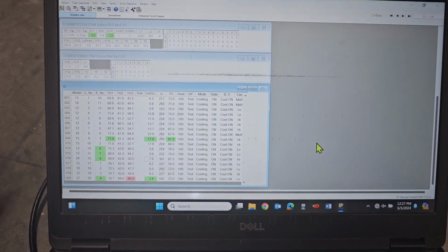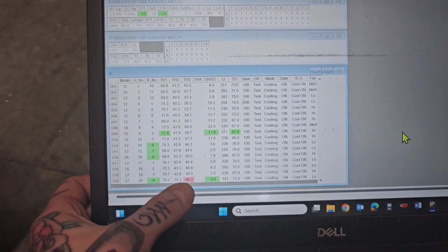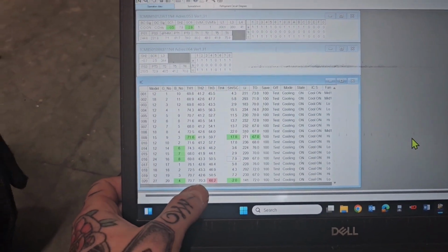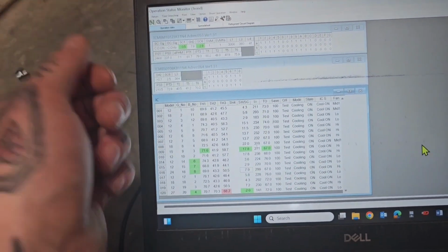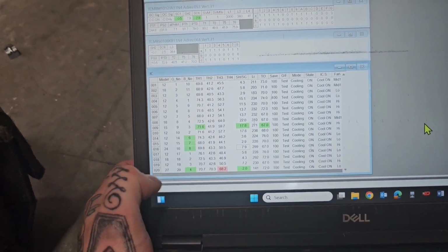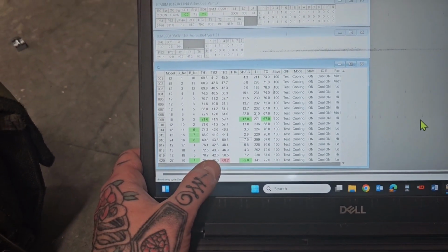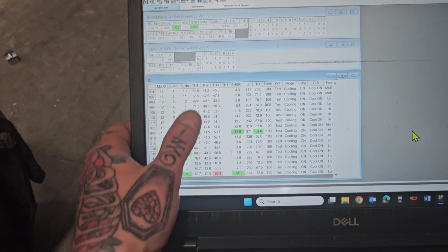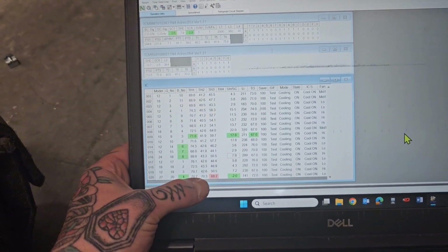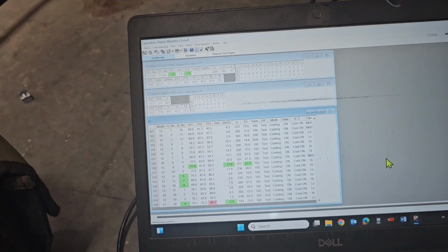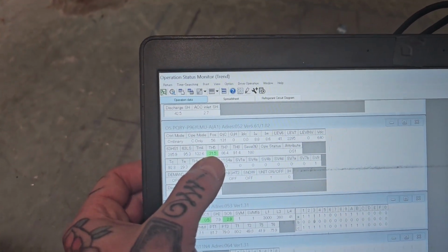If we go forward 10-15 minutes, you can still see, so we've got -2 degrees, but that doesn't matter because that port's closed. We've got 70 and 68. There's probably still liquid in that suction line boiling off because it's totally full of liquid because that valve is totally wide open. Okay. Now, some of our superheats did come down quite a bit, but it still didn't give me the increase in superheat at my TH5 that I would like to see.